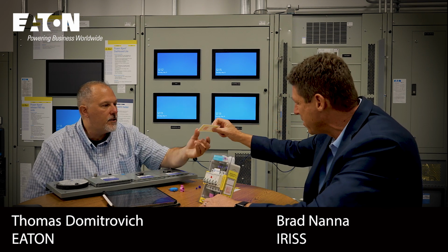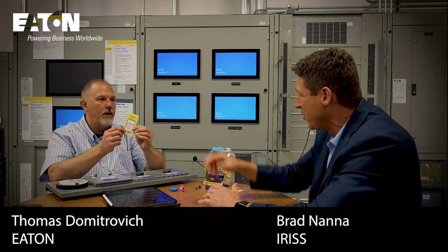It's a label, and when that square turns red, it means there was a thermal issue related to that bus bar. It starts off white, and red is the alert. When that square turns red, just from sticking this on the bus bar, it's a visual indicator that the bus bar got hot. It says: high temperature indicator, permanent color change to red if heated over 52 degrees Celsius, 126 degrees Fahrenheit.